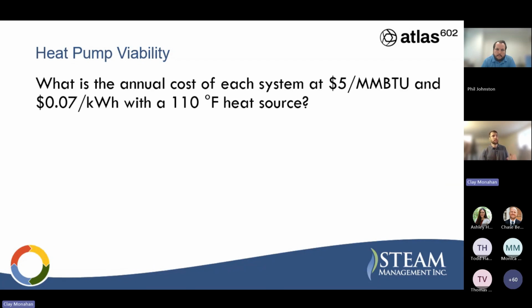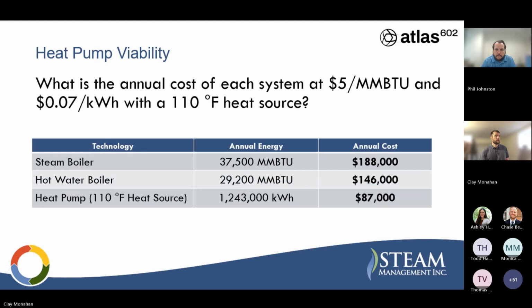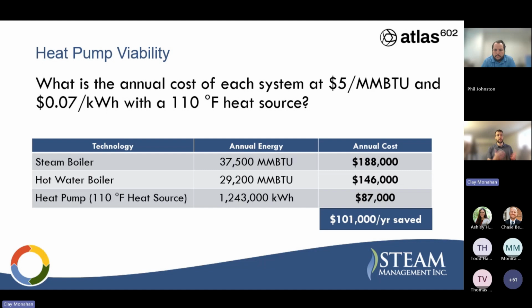So same pricing, but what if we have a 110-degree heat source instead of 80 degrees? Same as above for the first two above, and then $87,000 annual operating cost for that electricity that we have to purchase for this heat source. So we've doubled our savings, or actually over doubled our savings, just by going out and getting 30 degrees extra of heat.